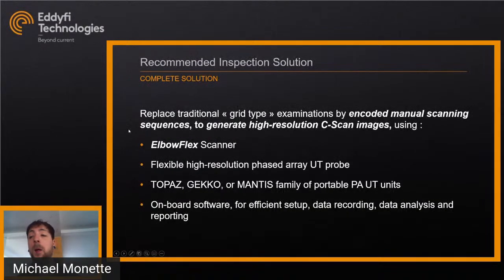To bypass all these pain points, Zetec came up with a scanner now in the Eddyfi lineup: the Elbow Flex scanner. It replaces the traditional grid-type examination for manual scanning, for example with a single probe or encoded manual scanning sequences, and it generates a high-resolution C-scan image. It uses the Elbow Flex scanner, the flexible high-resolution phased array probe made by Sensor Networks, and either a Topaz, Gekko, or Mantis PA UT unit. The onboard software is used for efficient setup, data recording, and data analysis.